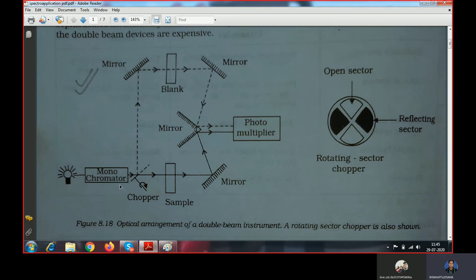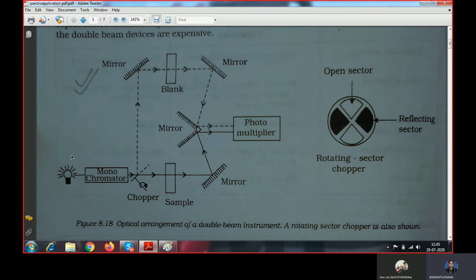Whenever you are using the light, we have to use a monochromator. For example, using UV light in the range of 180 to 400 nm, we take a BSA protein solution in one cuvette and blank water in another. A monochromator converts polychromatic light into monochromatic light. The polychromatic light contains all wavelengths — 180, 181, 182, etc. — passing through the monochromator. Since we command the monochromator to 280 nm, it transfers only 280 nm wavelength through both the sample and the blank, but not other wavelengths.